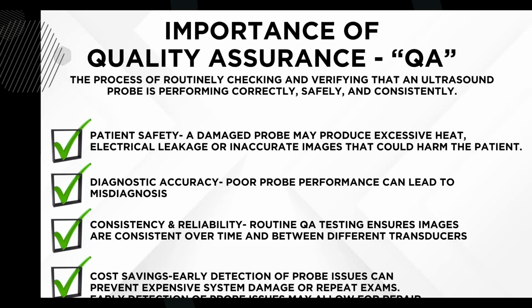Now, in order to effectively identify over time whether or not the transducer is degrading, you want to make sure that you're always in the same exam. So this particular one, you could be under small parts. You could use whatever preset that you want to use. Typically for the 12 linear, I would use a vascular preset and carotid when I did that. But anytime that I would go back and redo this test, I would make sure that I'm under the same preset as well. So in our service management software, we have a form, and this form, like I said, has a serial number, has our depth of penetration test. Under the depth of penetration test, it asks us for what preset that we were in. So we would have to write down, hey, we were in this preset.